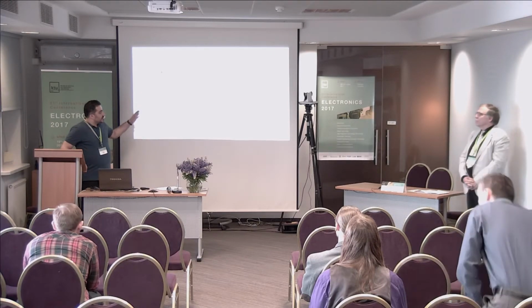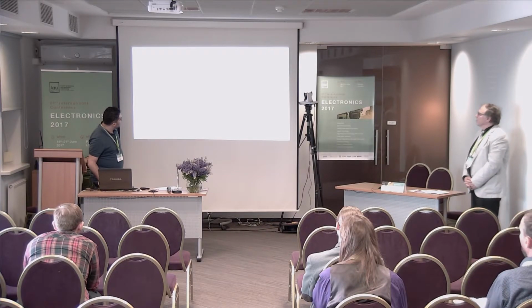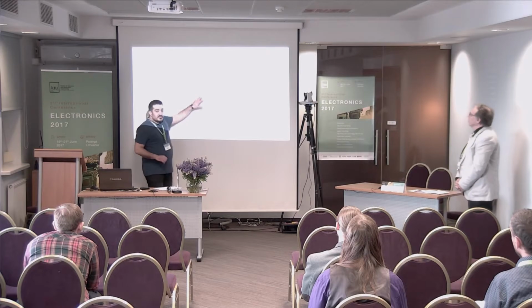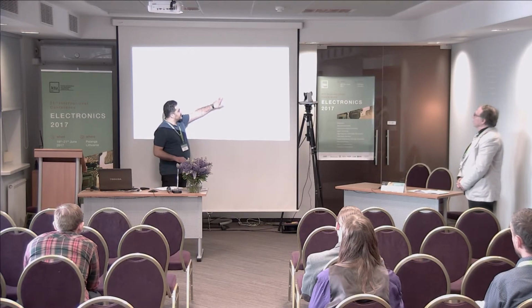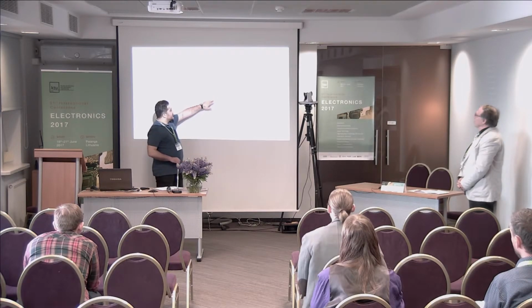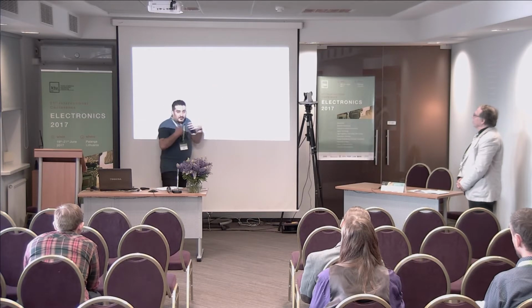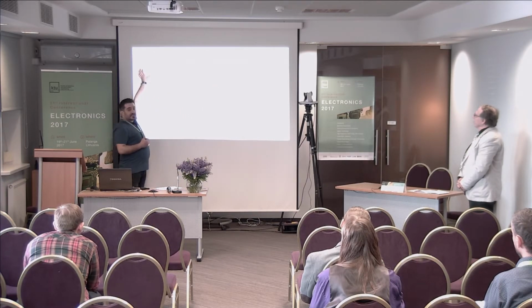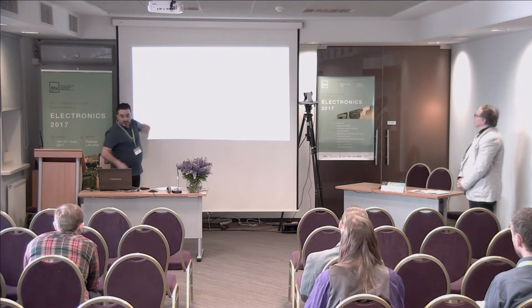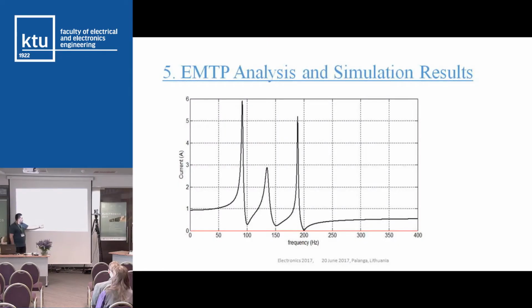Yes. I can come back to this here. I modeled this circuit, and I gave it a 1 ampere current here, and looked at how it changes on the network side. When we look at these results, we can see this graph, and this graph shows that the arc furnace load is not included in the system.